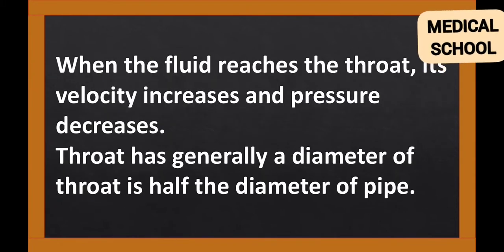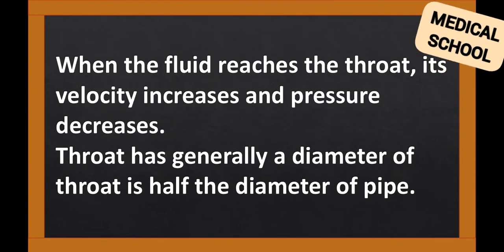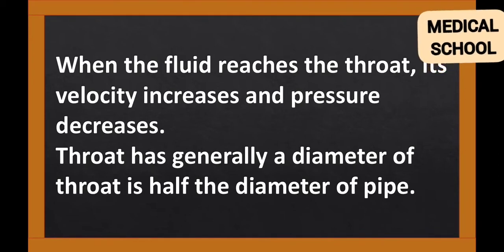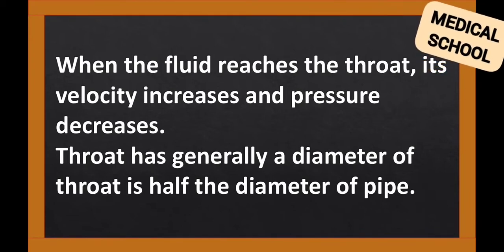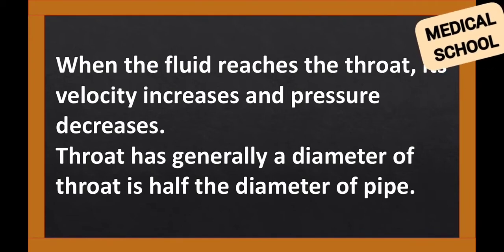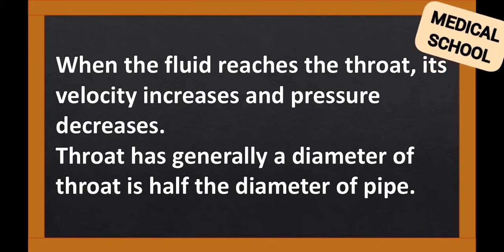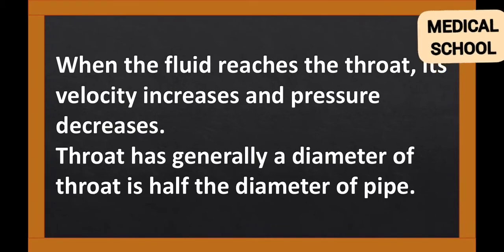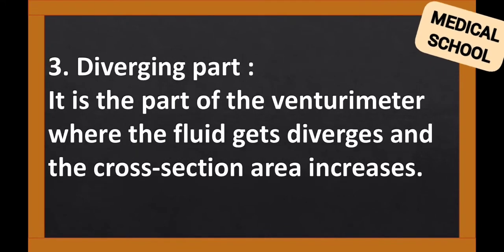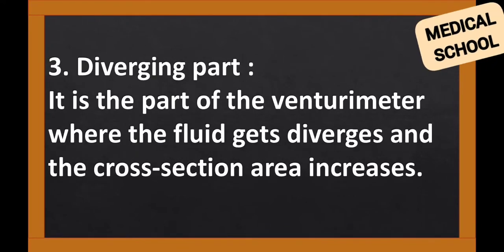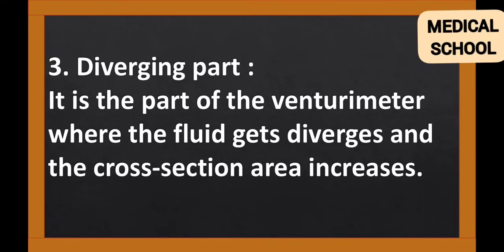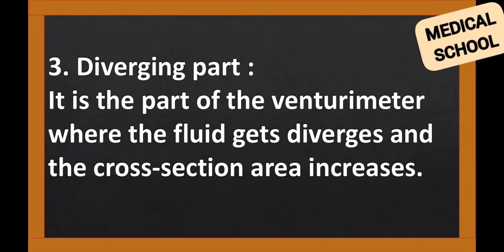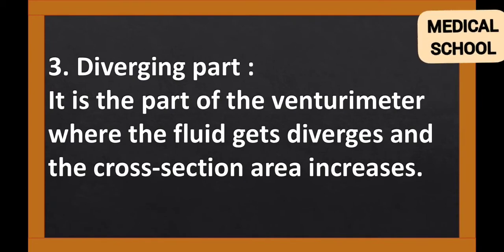When the fluid reaches the throat, its velocity increases and pressure decreases. The diameter of the throat is generally half the diameter of the pipe. The diverging part is the part of the Venturi Meter where the fluid diverges and the cross-section area increases.